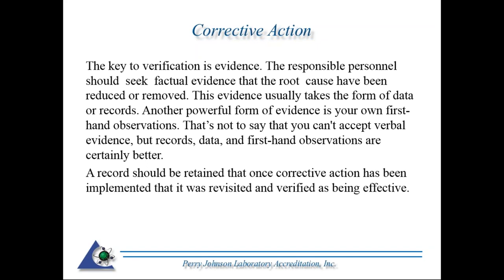So looking at a corrective action record, we see everything implemented, the corrective action actually implemented. What I don't like to see is it verified as being effective one day after the fact that it was implemented. Let's say, for example, you had customer complaints that warranted a corrective action that had to do with turnaround time. Hence, you implemented a corrective action that put more resources into calibration, hence reducing the turnaround time. It's going to be a little while before you can actually determine whether or not that corrective action has been effective.